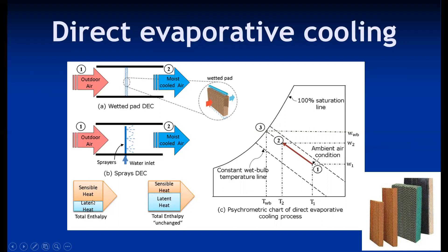In adiabatic humidification, at the inlet the air has a higher amount of sensible heat and lower latent heat. As it flows through the wetted pad, sensible heat is reduced and latent heat increases, so total enthalpy remains constant. If the wetted pad or sprayed water temperature equals the wet bulb temperature of entering air, this ideal process occurs. If below WBT, enthalpy rises; if above WBT, enthalpy drops. The ideal adiabatic humidification process has no change in enthalpy. Direct evaporative cooling is mainly used in desert conditions when the atmosphere is hot and dry.